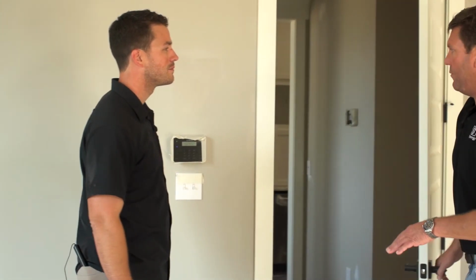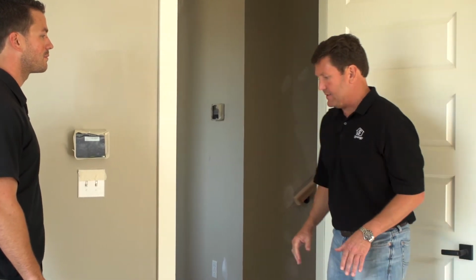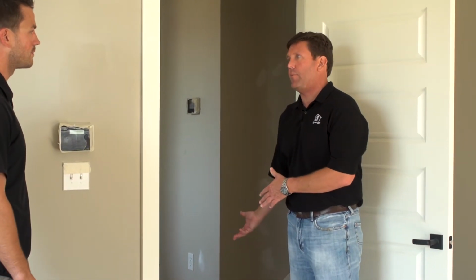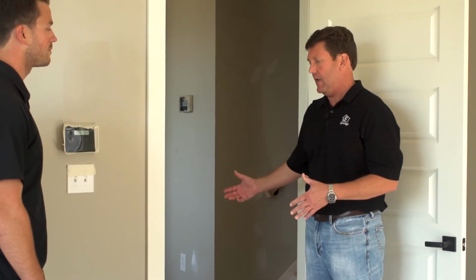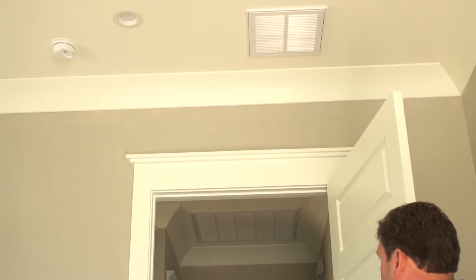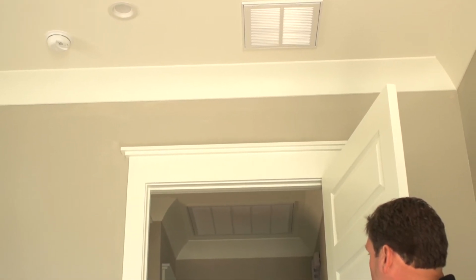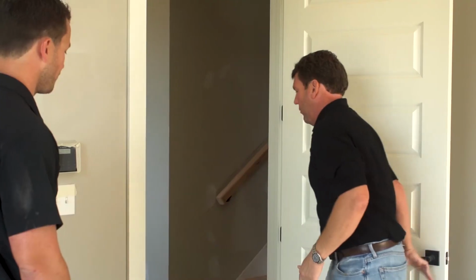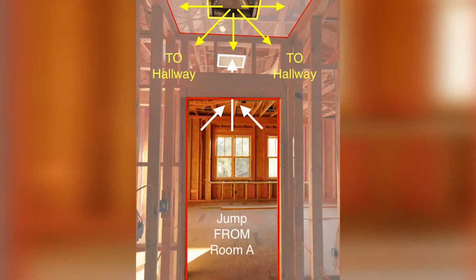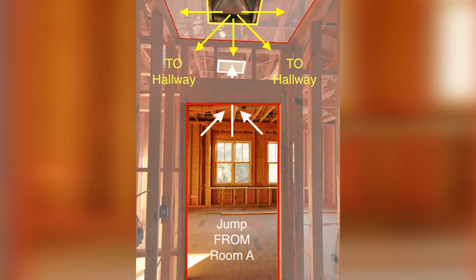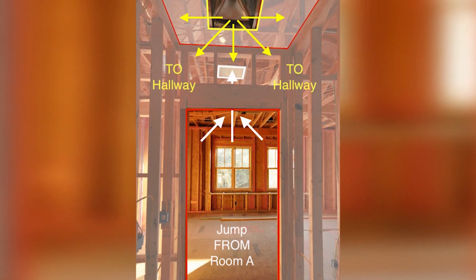I can show you through when we test out houses, we usually close the door, drop a manometer, and measure. But right now there's no air flowing through that duct, so all the air goes straight into the return. When we close this door, all it does is take the air from this room back to that return.